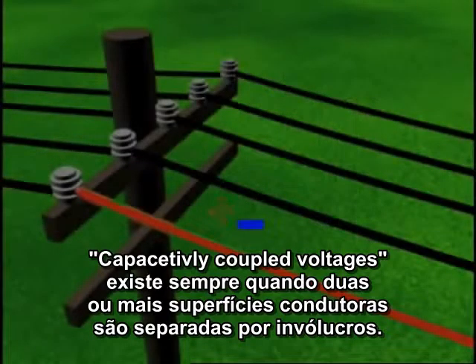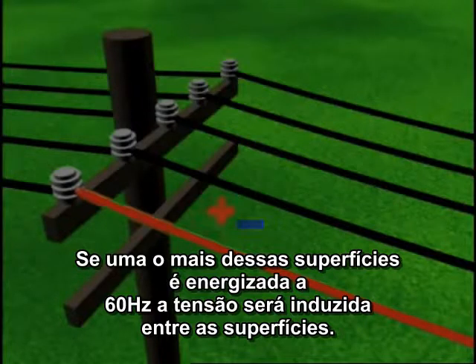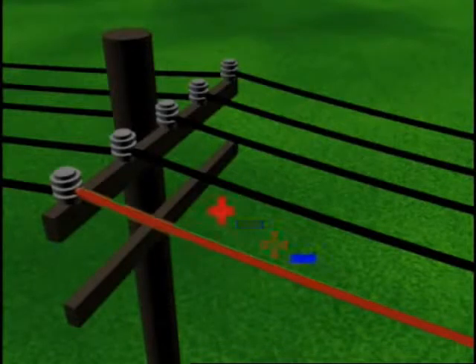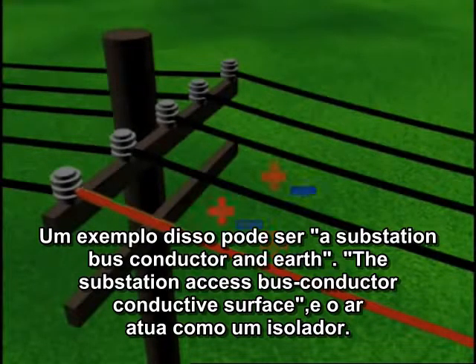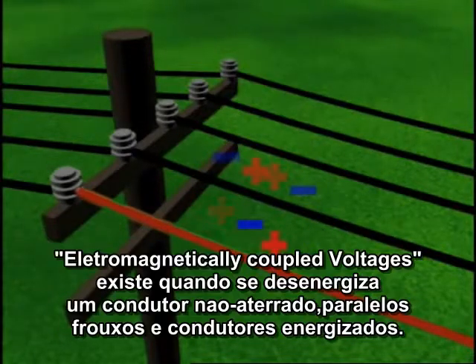Capacitively coupled voltages exist whenever two or more conductive surfaces are separated by insulation. If one or more of the surfaces is energized, a 60 Hz voltage will be induced between the surfaces. An example of this might be a substation bus conductor and earth. The substation acts as the bus conductor's conductive surface, and the air acts as the insulator. Steady-state charging currents will flow due to this capacitive effect.